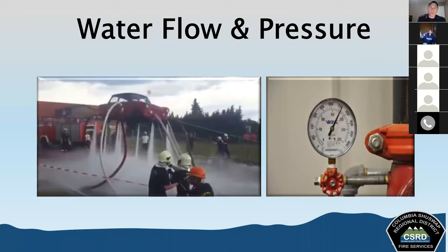So it moves into our pumps. Hydrants wouldn't be operational without static pressure. We can measure static pressure a couple of different ways, by placing a pressure gauge on the hydrant outlet and opening the hydrant valve. Then there's normal operating pressure, which is the amount of pressure in the distribution system during normal consumption.